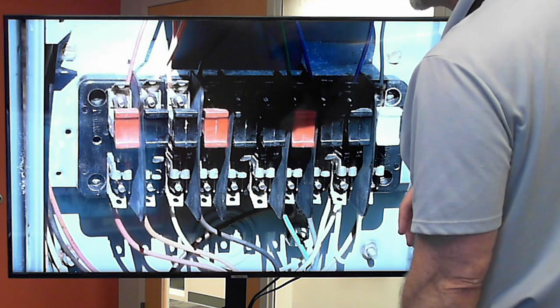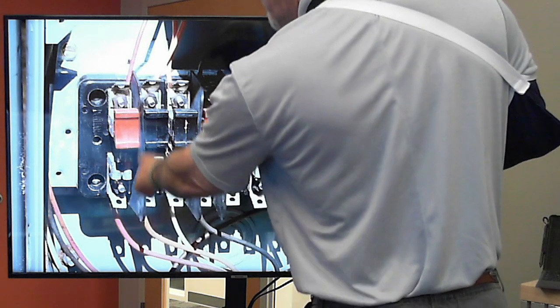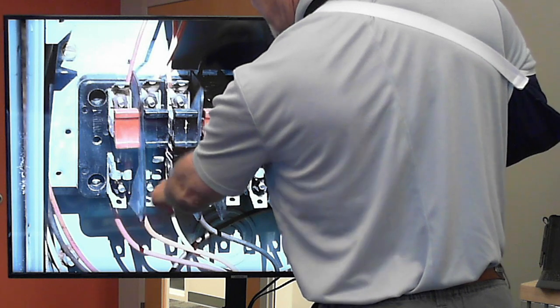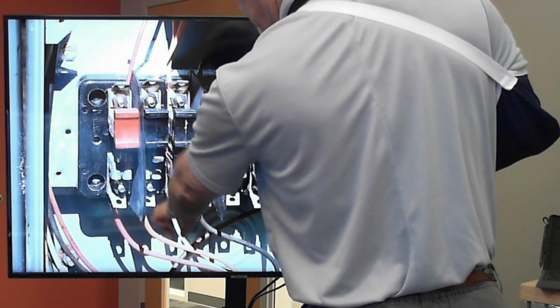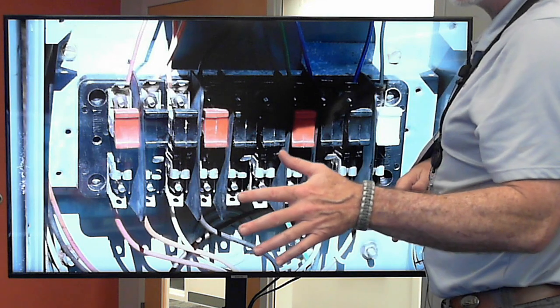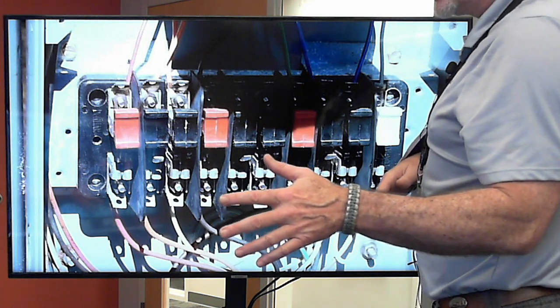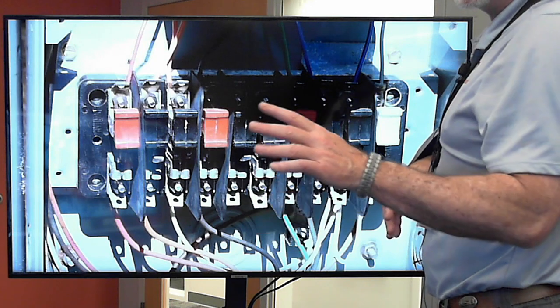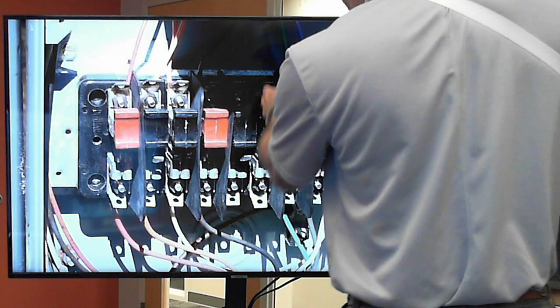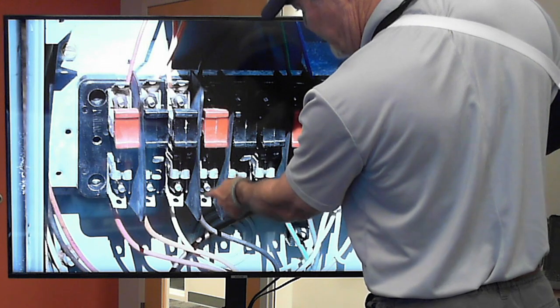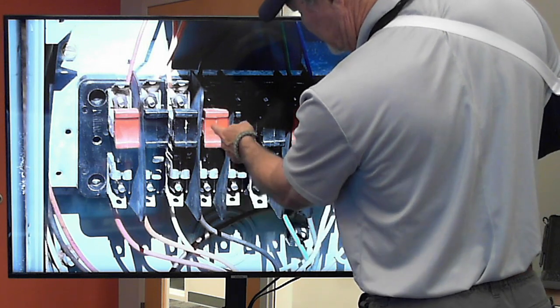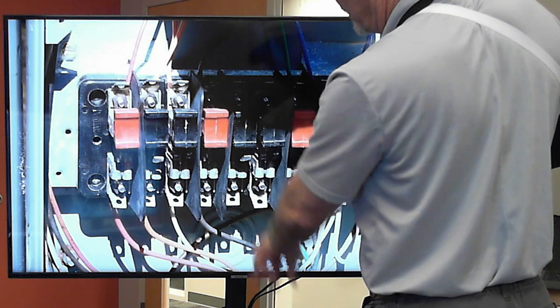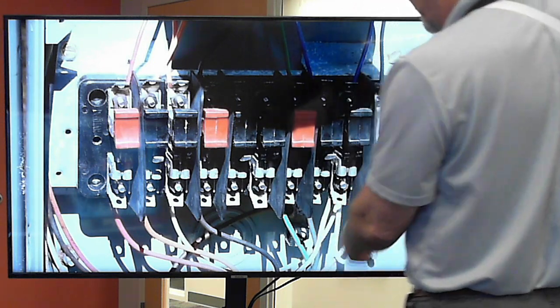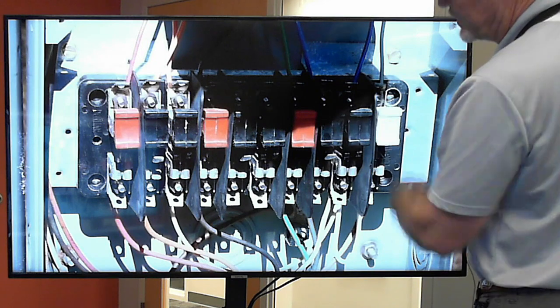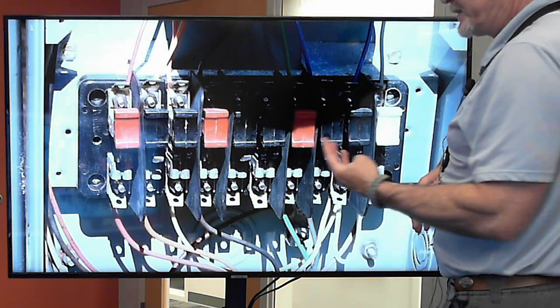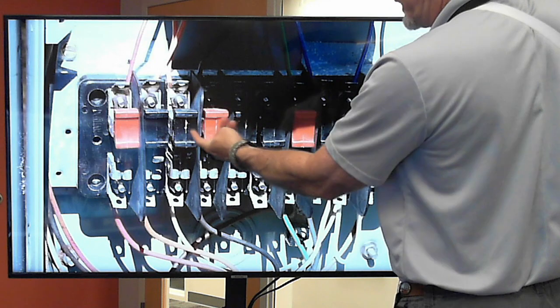So when we look at the assessment here, I've got my A phase voltage and A phase currents, and I can see my connections there. The B phase is the key for us on a 5S delta, because we want to see if it's open or grounded. I do have a voltage connected on B phase, but nothing on currents there. Then on C phase I've got both voltage and current. So as we said earlier, we've got 3 voltages but only 2 currents.